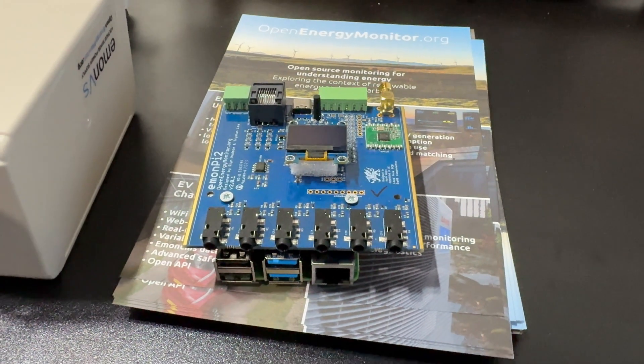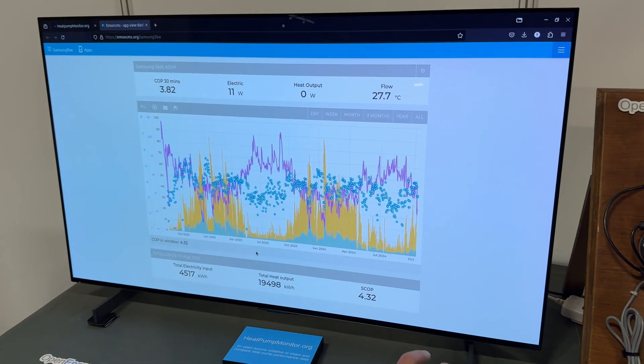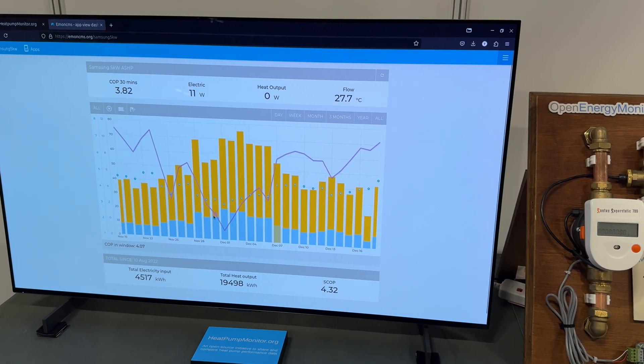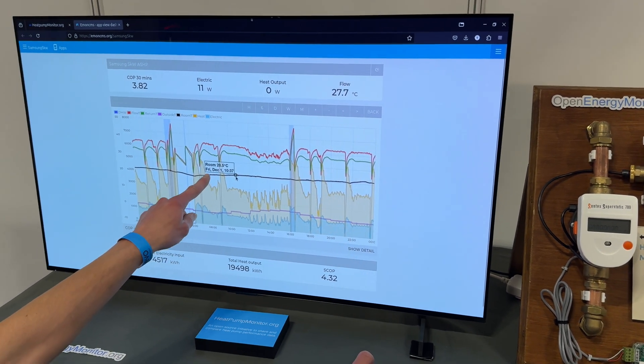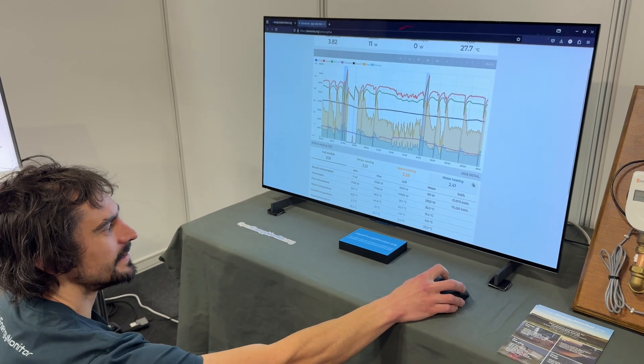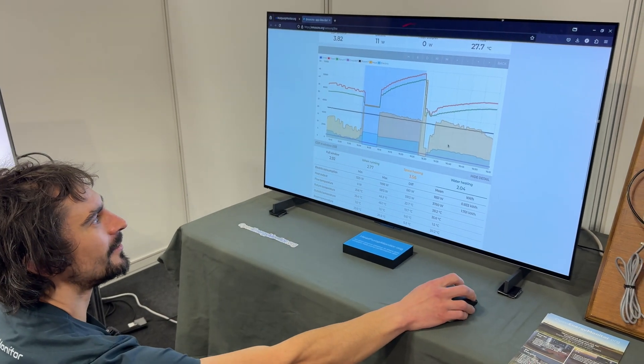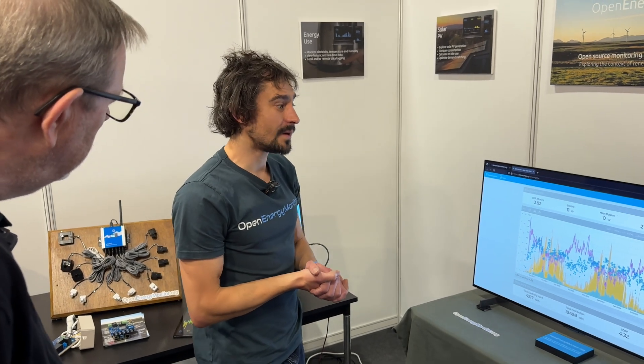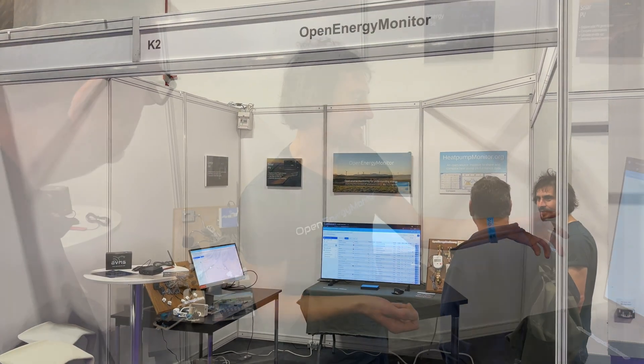And this can be done wirelessly? Yeah. So if I go into one of these systems — this is my own system — you can see two years of heat data, winter putting in heat. The purple line here is the outdoor temperature, so you can see as the outdoor temperature drops the heat pump has to put in more heat. We can zoom right in and look at the coldest day of the year when it went down to minus three degrees and see how much heat the heat pump is putting in, and what the internal room temperature was. It's basically demystifying what the heat pump is doing at any given time. You can see the COP you're getting for hot water — that's a hot water cycle where it's heating up the tank. It's a really useful tool to help you optimize your heat pump. You can make a change on the control, maybe drop the flow temperature or change your schedule, and see if that's made it work better.